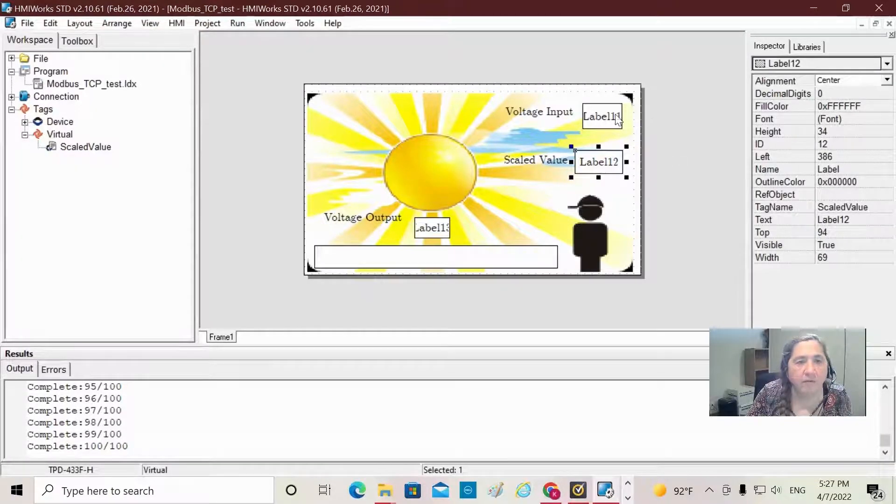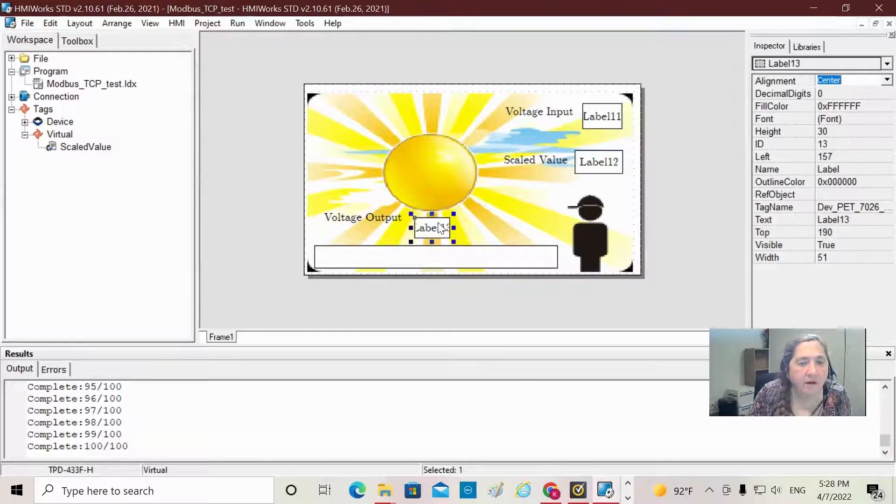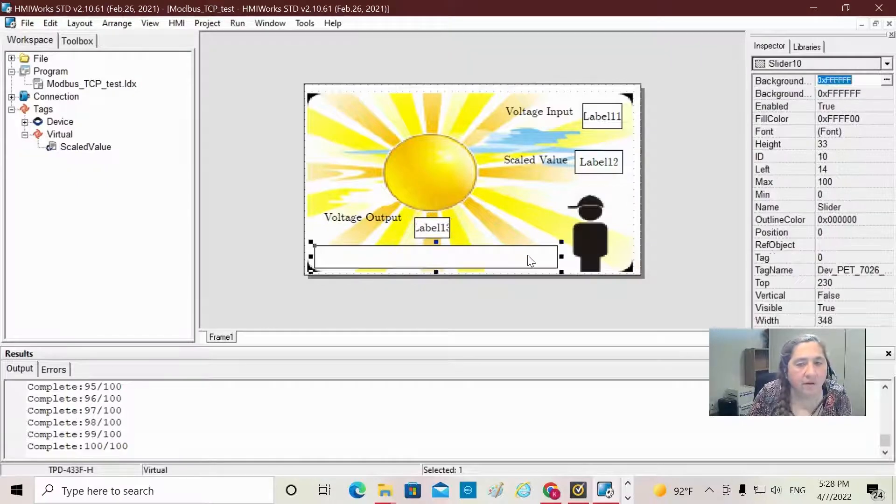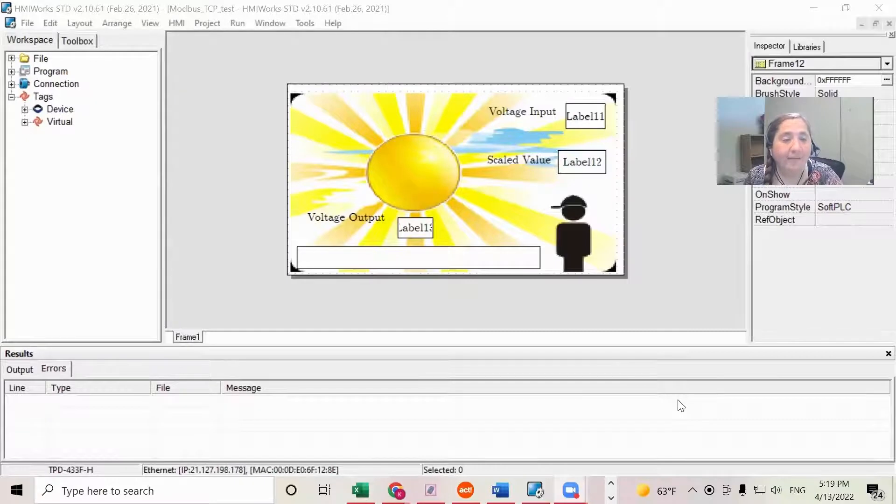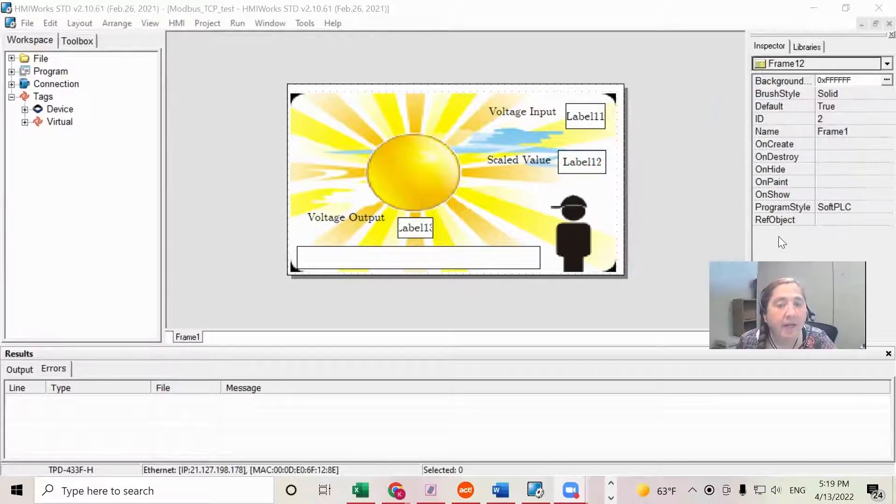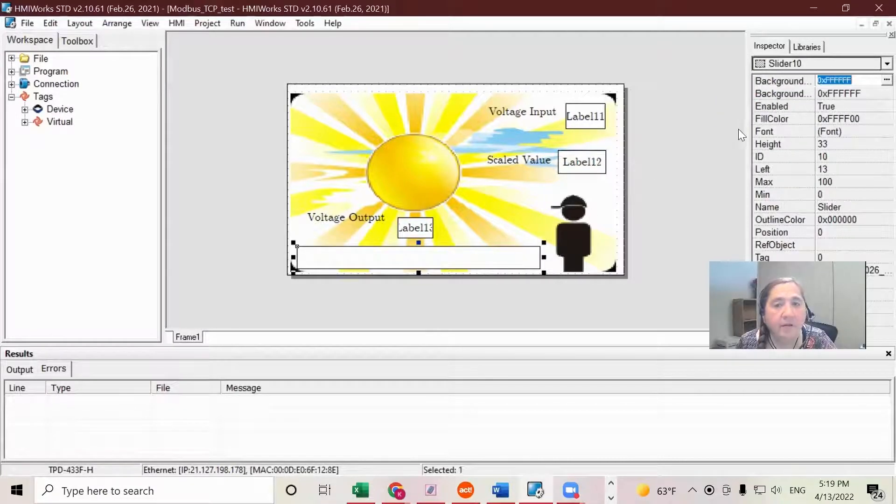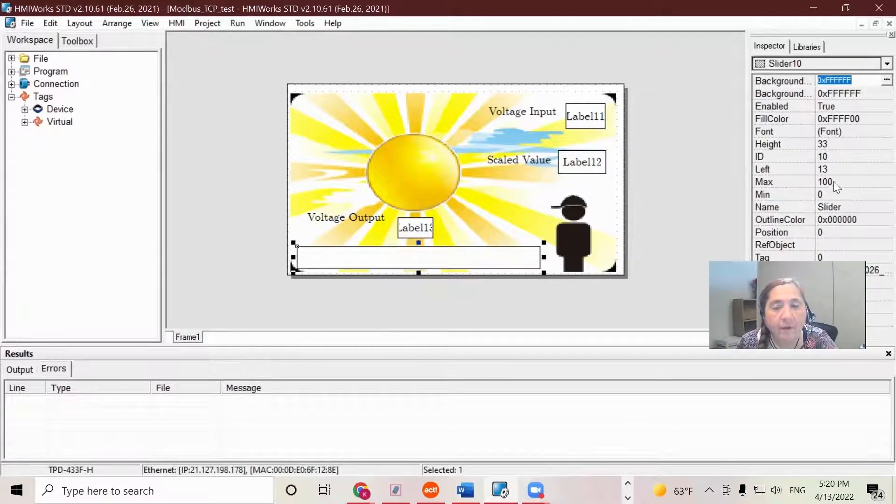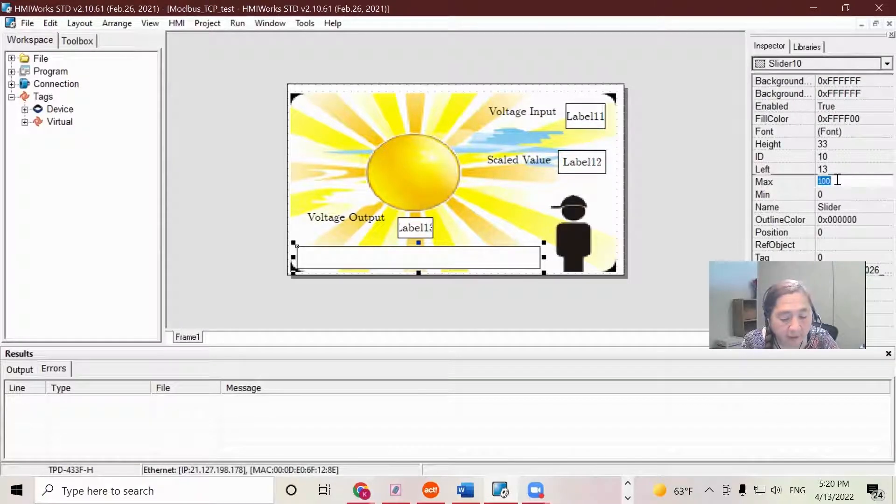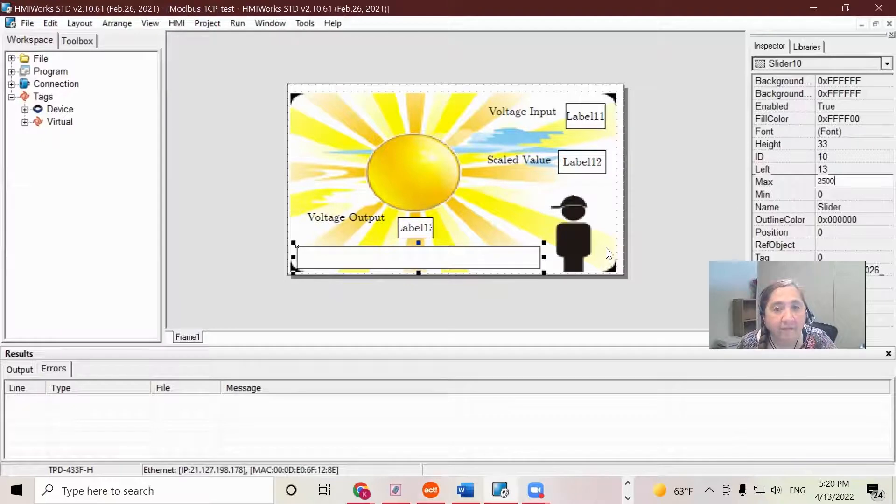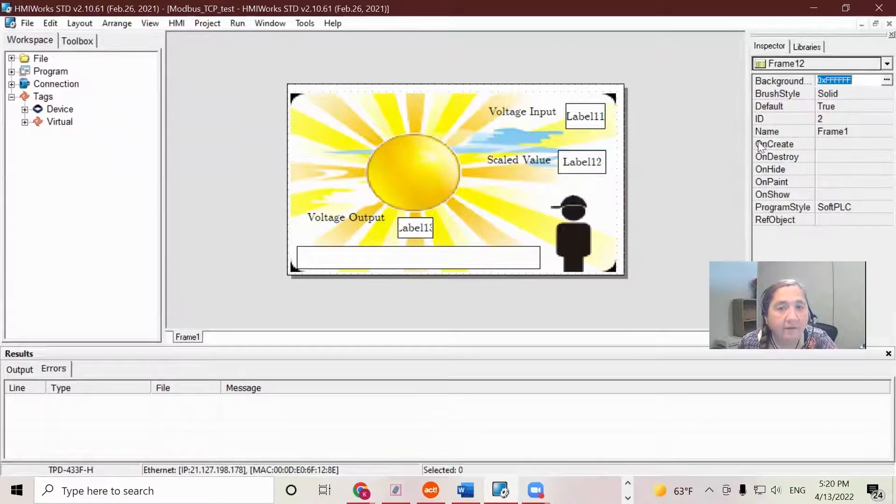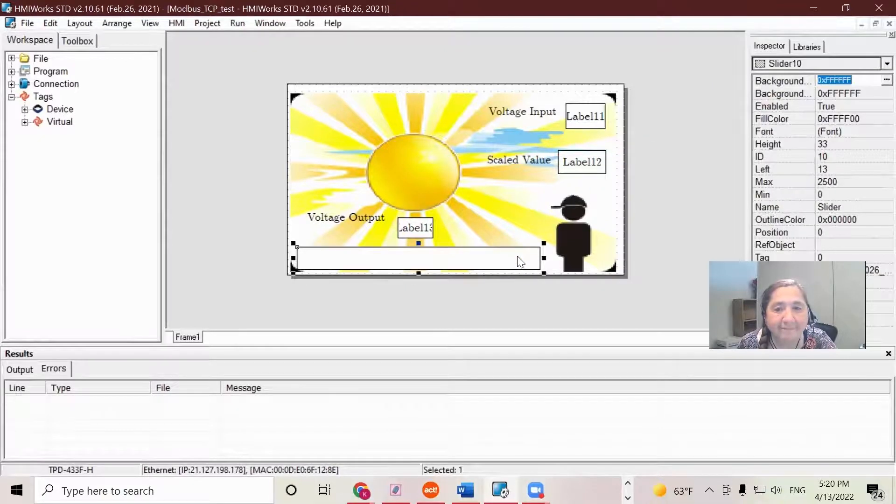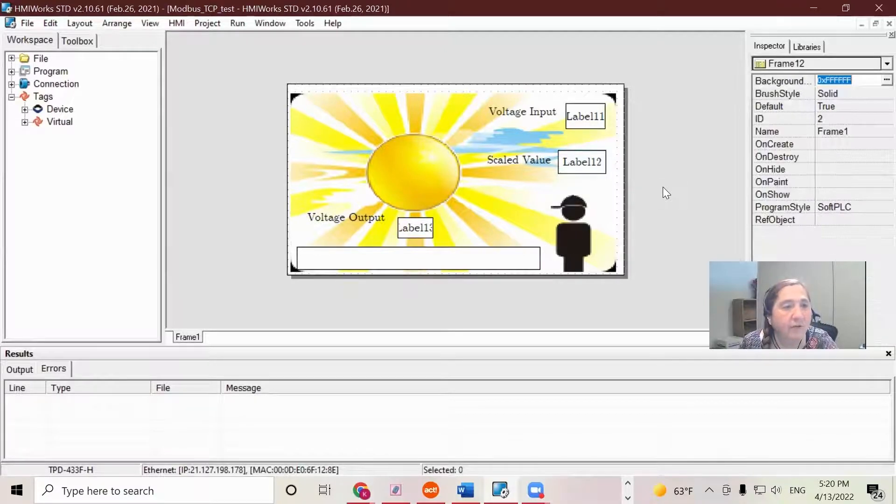You can see over here, your properties are filled in. This is a scaled value, fill label 12, label 11. There's a tag there for that one. And then here for label 13, you've got the tag for that one. And here I've got my tag in there. One more thing I need to do before I can download to my TPD is I want to fix my scaling. I look at right here, the minimum on my slider I want to be zero. But the maximum I want for my 2500 millivolts or two and a half volts for my scaling on my slider. So now I've got that. And there we are on that.